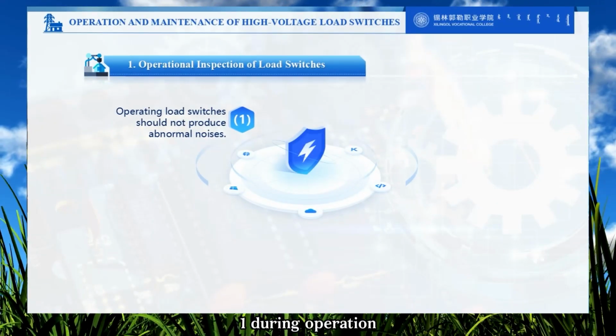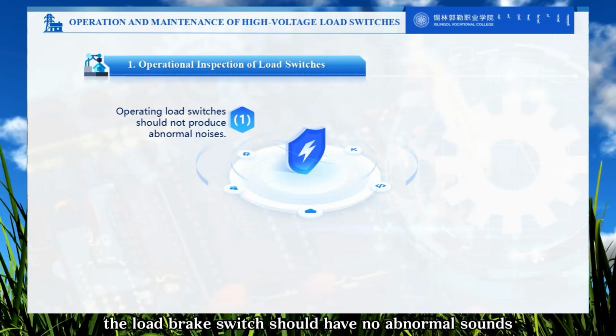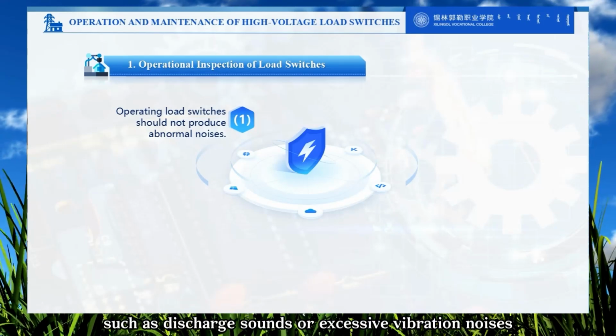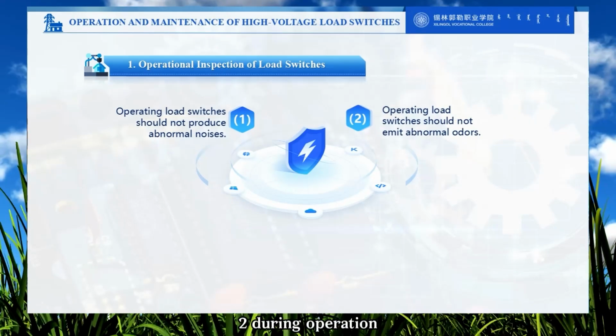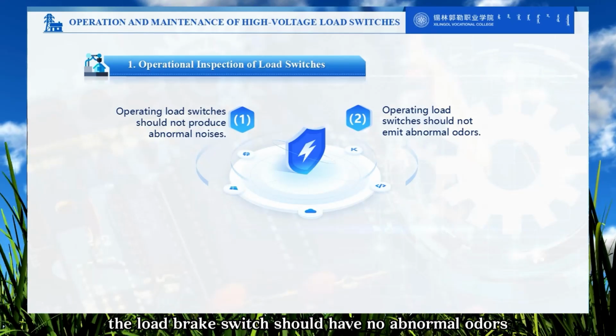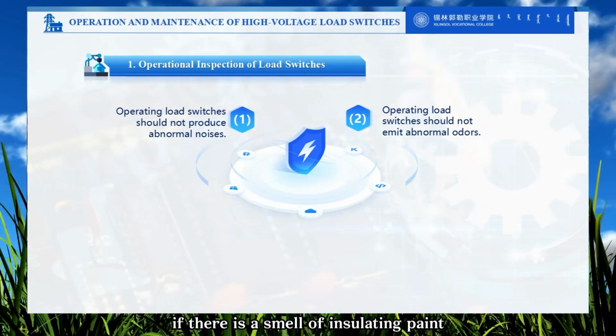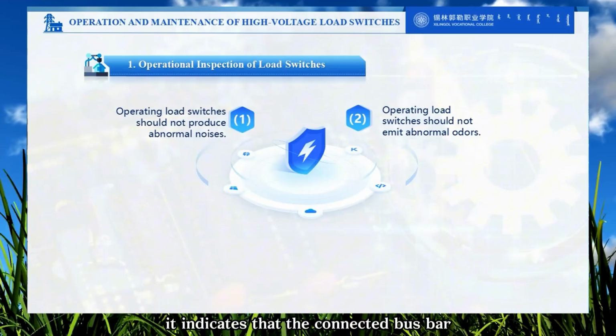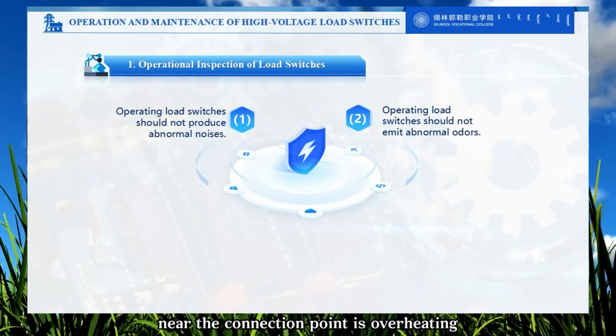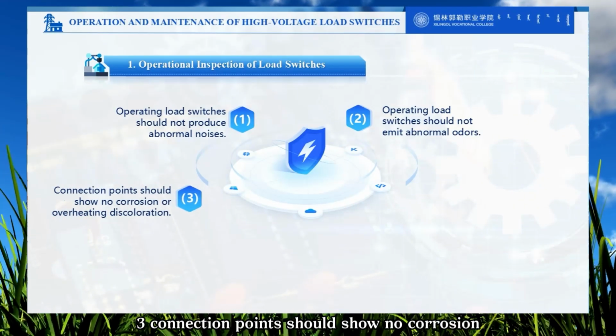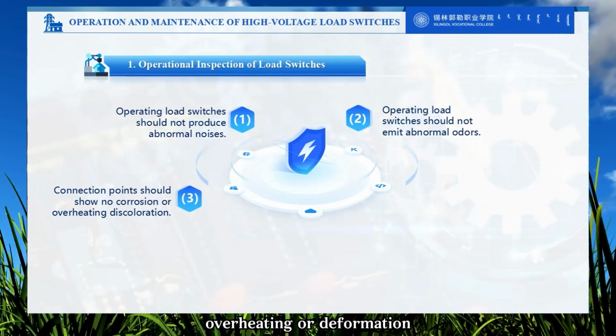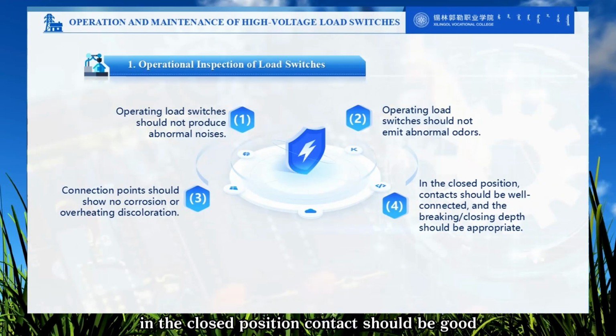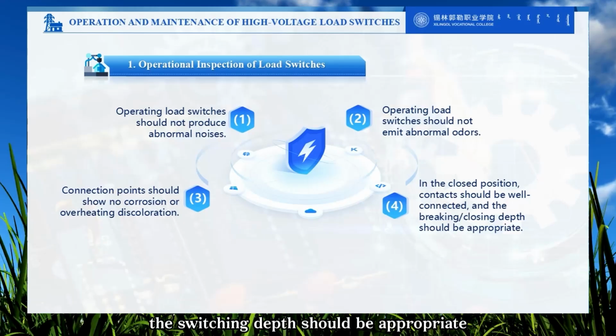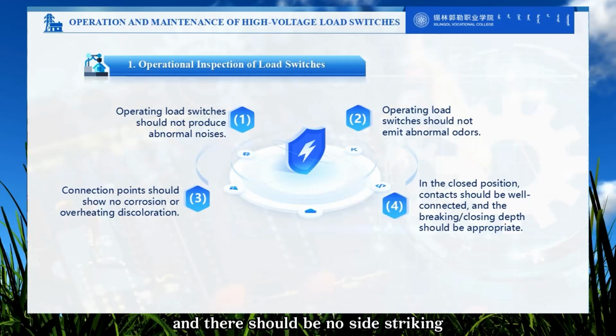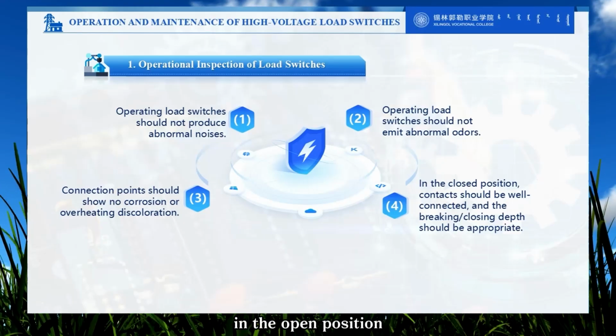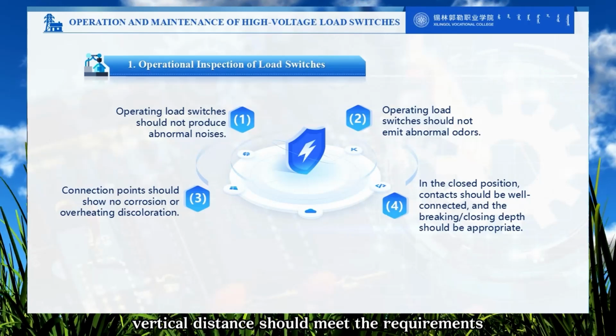1. During operation, the load break switch should have no abnormal sounds, such as discharge sounds or excessive vibration noises. 2. During operation, the load break switch should have no abnormal odors. If there is a smell of insulating paint or plastic casing, it indicates that the connected bus bar near the connection point is overheating. 3. Connection points should show no corrosion, overheating, or deformation. 4. In the closed position, contact should be good, the switching depth should be appropriate, and there should be no side striking. In the open position, the separation vertical distance should meet the requirements.